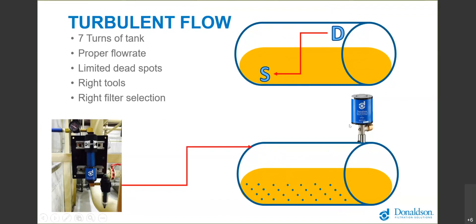This tank breather does three micron particle filtration and water removal, so the water is not going to come back in. We continuously purge dry air over that tank and the dissolved water that's in the fuel is actually going to come up to the air interface and push it out the tank. The only time this doesn't work is if you have one or two inches of water at the bottom of the tank. It's pretty hard for that water that's already fallen out of the fuel to dissolve back into the diesel and then go out of the tank.